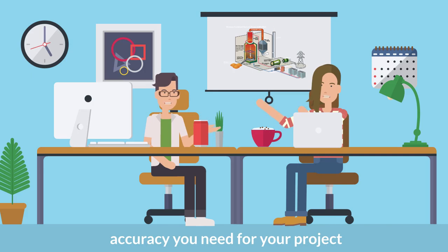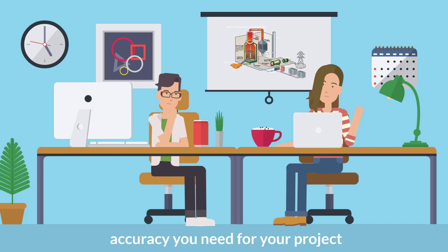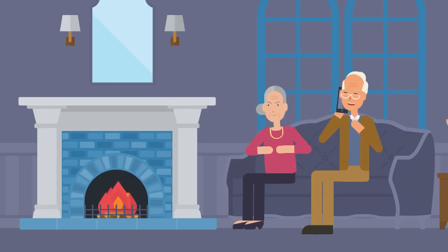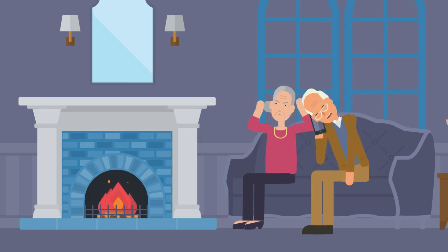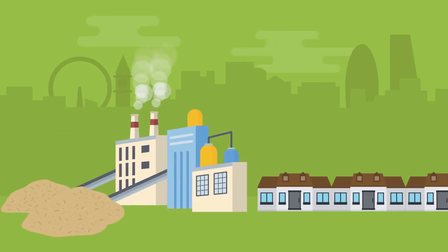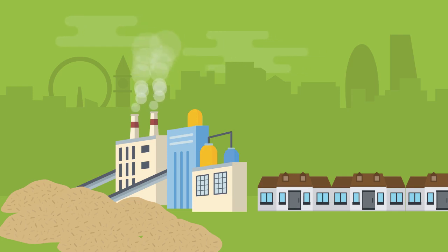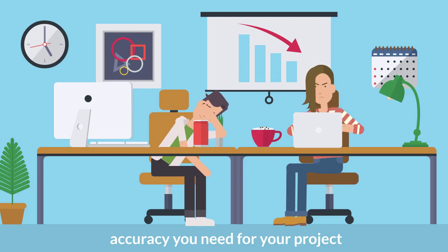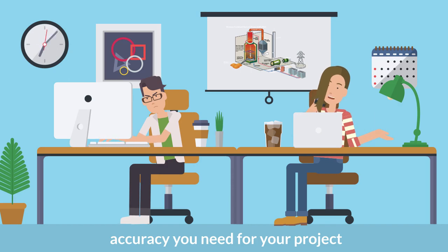The first decision you must make is the accuracy you need for your project. The higher the accuracy, the greater the difficulty of the calculations. When sizing the power system, the goal is to supply all the energy that is needed when needed. Then, you may be tempted to oversize the system. The bigger, the better. However, you should keep in mind that oversizing electricity sources decreases the efficiency and the economic viability of power systems. Therefore, you need a certain degree of accuracy to ensure the realisticness of your design.